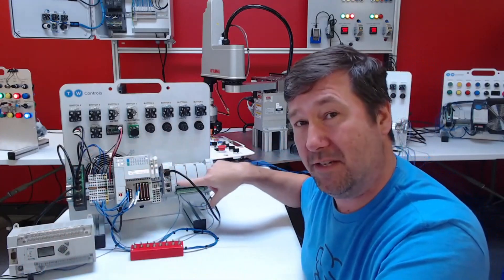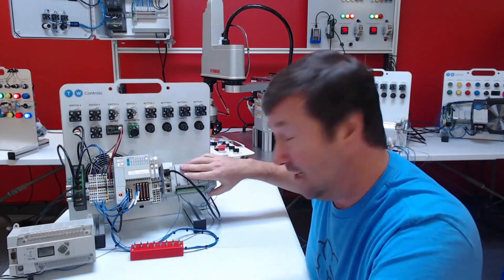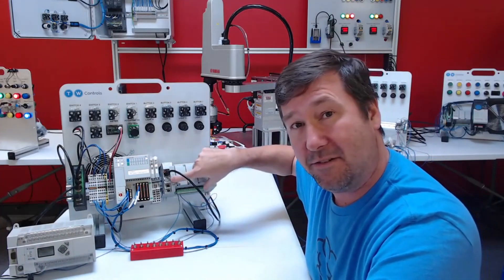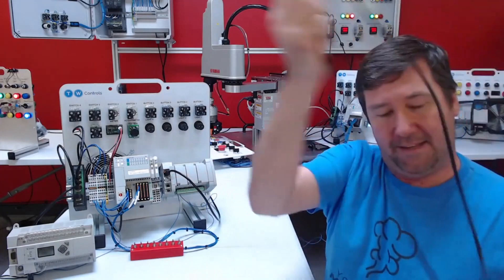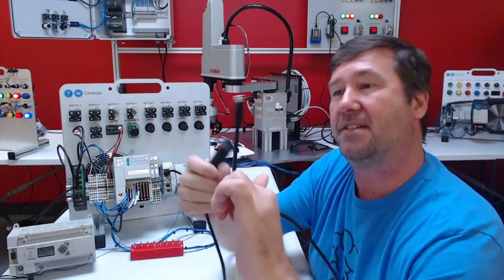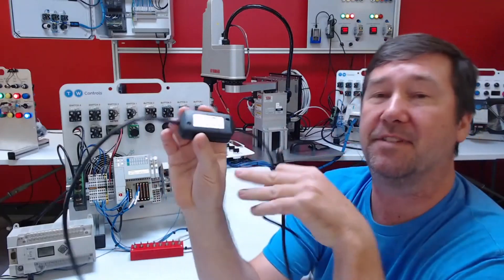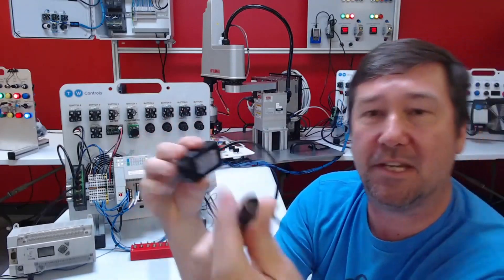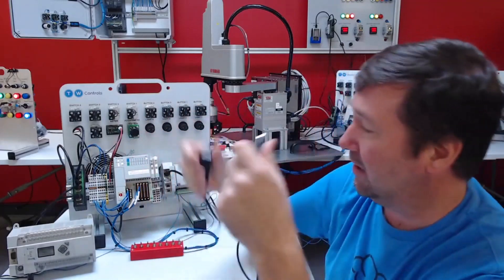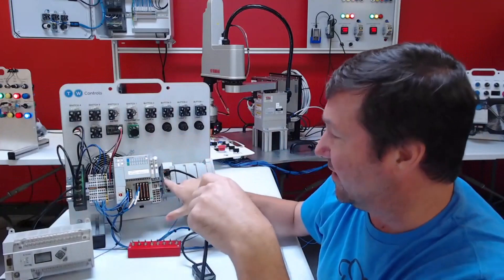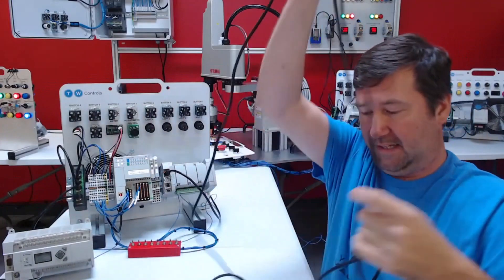So this is a Micro 850 PLC, it's a modern PLC. And you'll notice it's got a serial cable. Now it has the round connector. And that round one is going to be our 1747, I'm sorry a 1761-CBL-PM02. That's going to be the round one. You're going to find it on a lot of your Micrologix PLCs and you'll also find it on many of your modern PLCs.